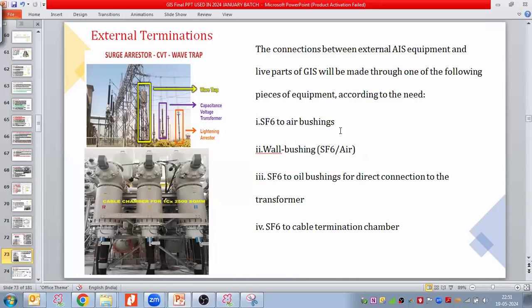So we can take the SF6 to air bushing. In this example photo, where my cursor is, this is the SF6 to air bushing. Sometimes we take a wall bushing, which is installed directly on the wall of the GIS building. We can also take SF6 to oil bushings for direct connection to the transformer bushings, and SF6 to cable termination chambers. Here in this example we have the cable chamber, and in this cable chamber the cable is terminating, right?